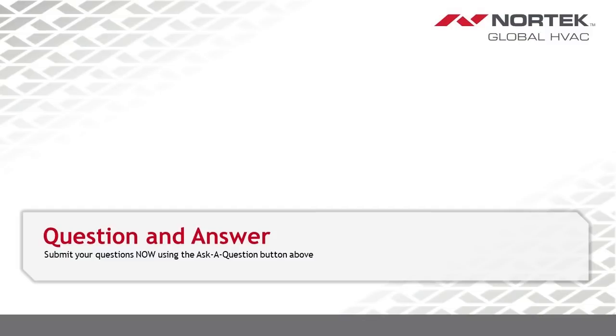Do these gas furnaces have or need a 5-ton blower kit? Not as of today. All the testing we're doing matches, again, 400 CFM per ton as the target for the 5-ton furnace matches, so not today.